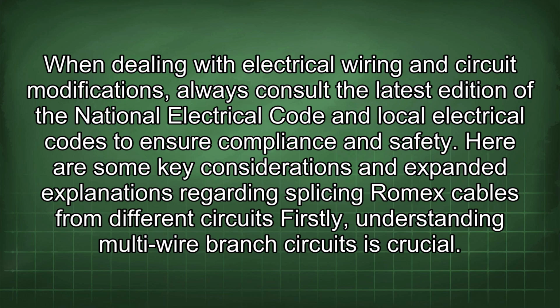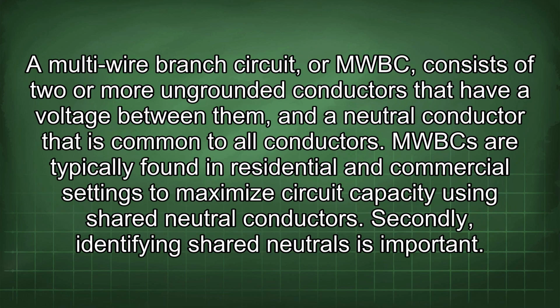When dealing with electrical wiring and circuit modifications, always consult the latest edition of the National Electrical Code and local electrical codes to ensure compliance and safety. Here are some key considerations and expanded explanations regarding splicing Romex cables from different circuits. Firstly, understanding multi-wire branch circuits is crucial. A multi-wire branch circuit, or MWBC, consists of two or more ungrounded conductors that have a voltage between them, and a neutral conductor that is common to all conductors. MWBCs are typically found in residential and commercial settings to maximize circuit capacity using shared neutral conductors.